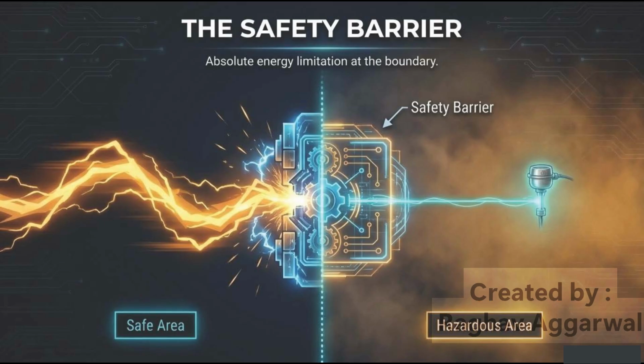Let us see the concept of safety barrier now. The barrier sits between the safe area and the hazardous area. Its function is to enforce absolute energy limitation at this boundary. This barrier can be a non-galvanically isolated barrier, that is a Zener diode, or a galvanically isolated barrier, that is a transformer. In simple terms, the barrier controls the amount of electrical energy that can pass toward equipment in the hazardous zone.